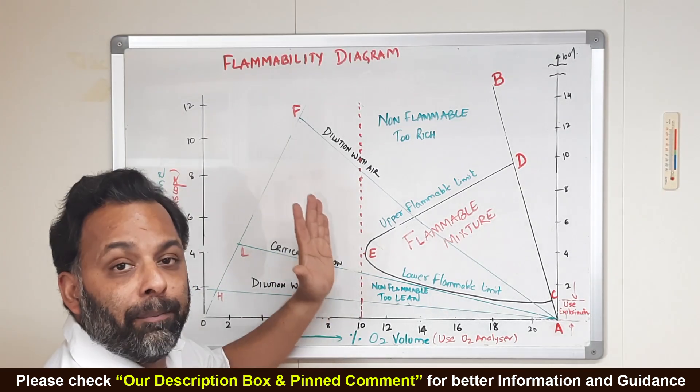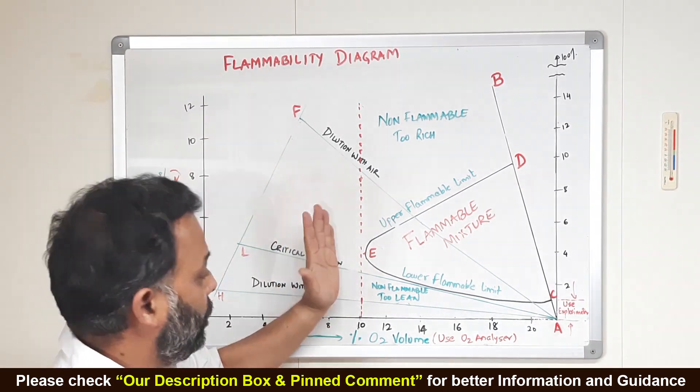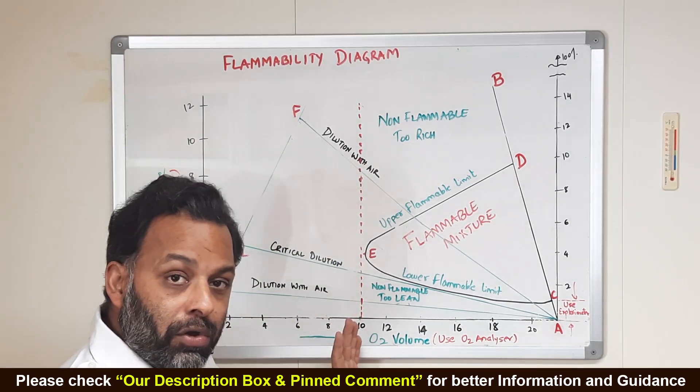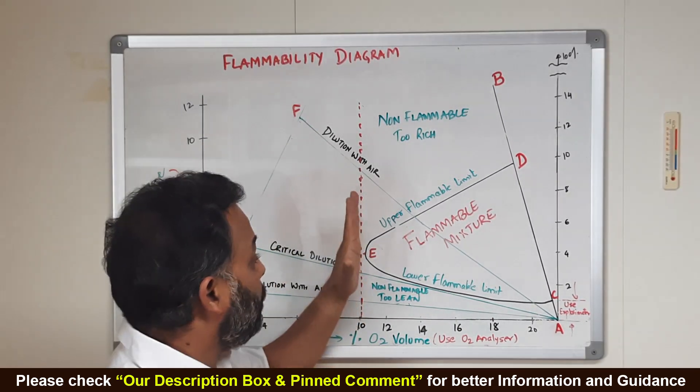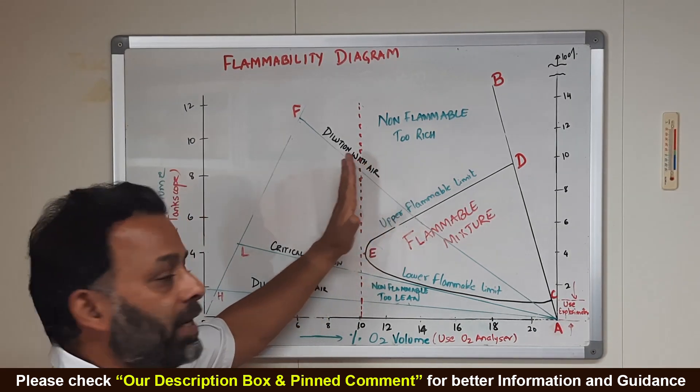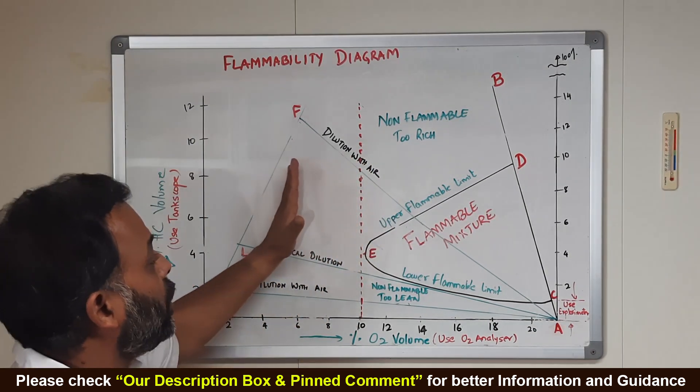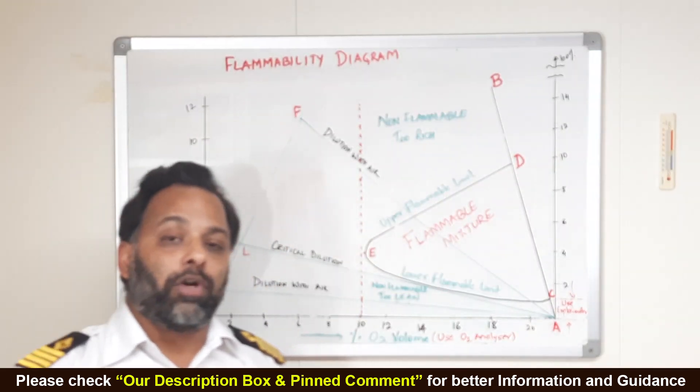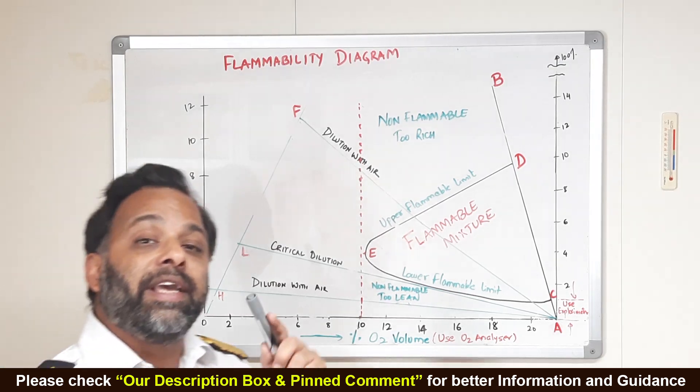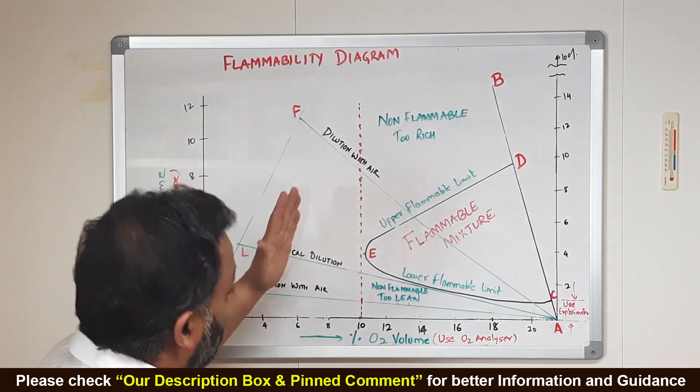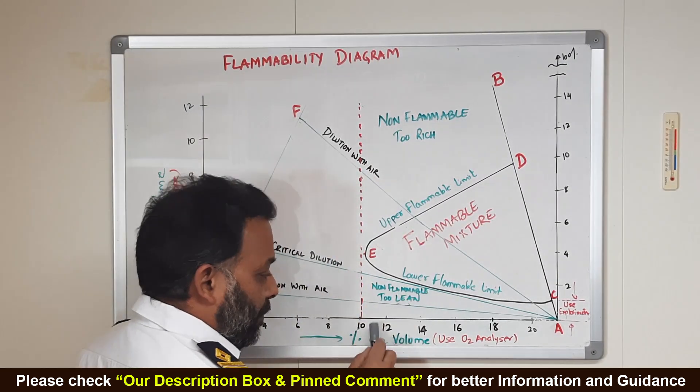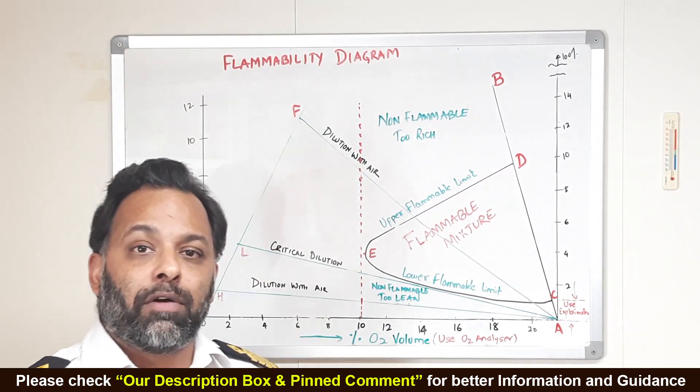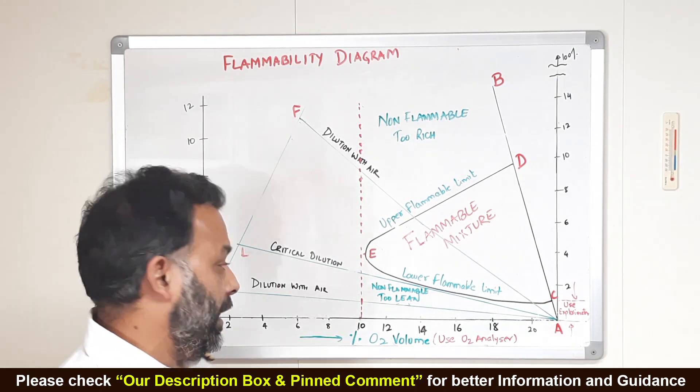Now, this is the minimum point at which there is sufficient oxygen for a fire to take place. If we keep on introducing inert gas further than this, we will come into a region, we will come to an area where the fire cannot take place because the amount of oxygen in the system is less than what is required. This point E is somewhere around 11% of oxygen. IMO says, if we have less than 8% of oxygen, we are absolutely okay and no fire will take place.